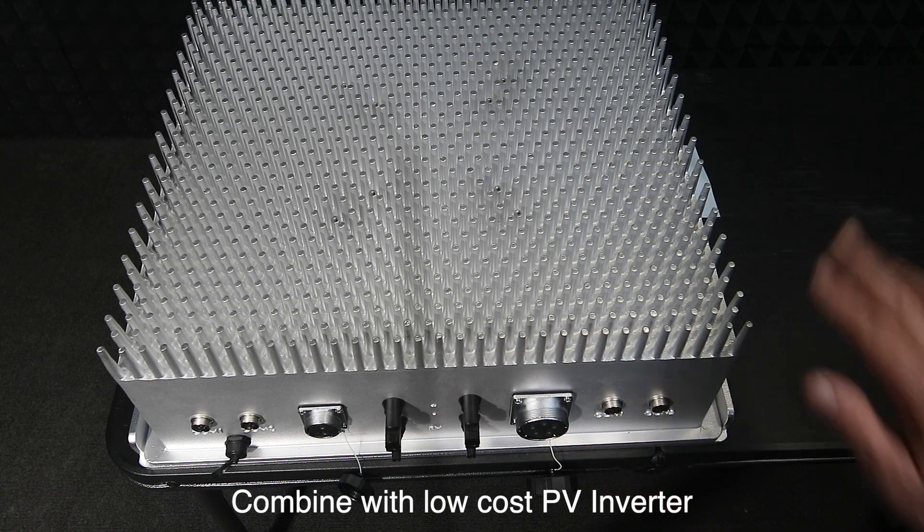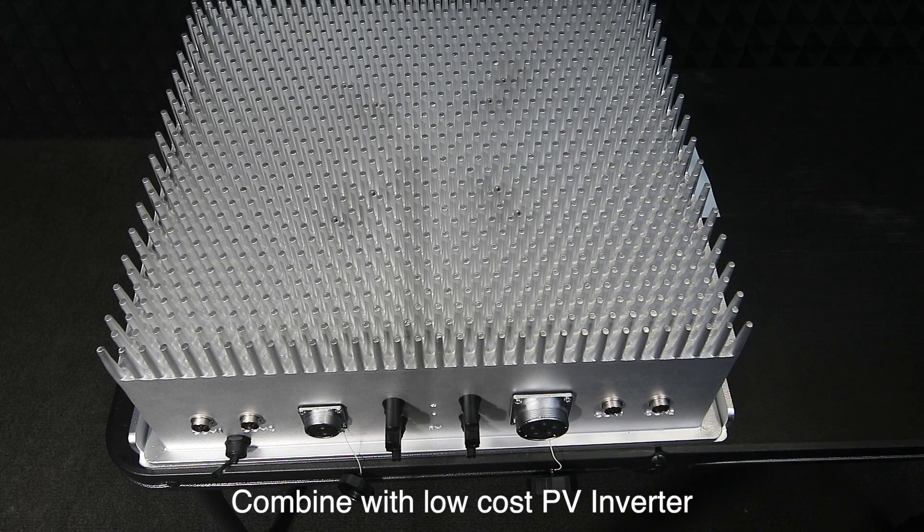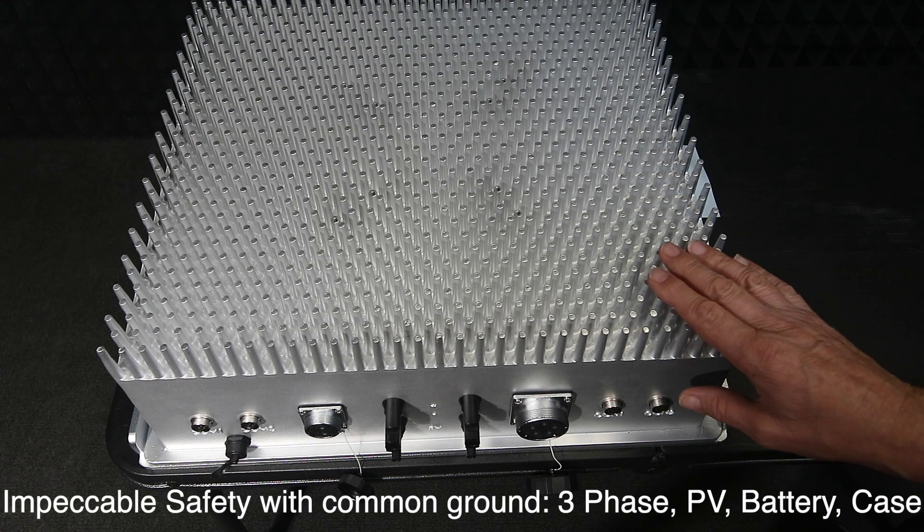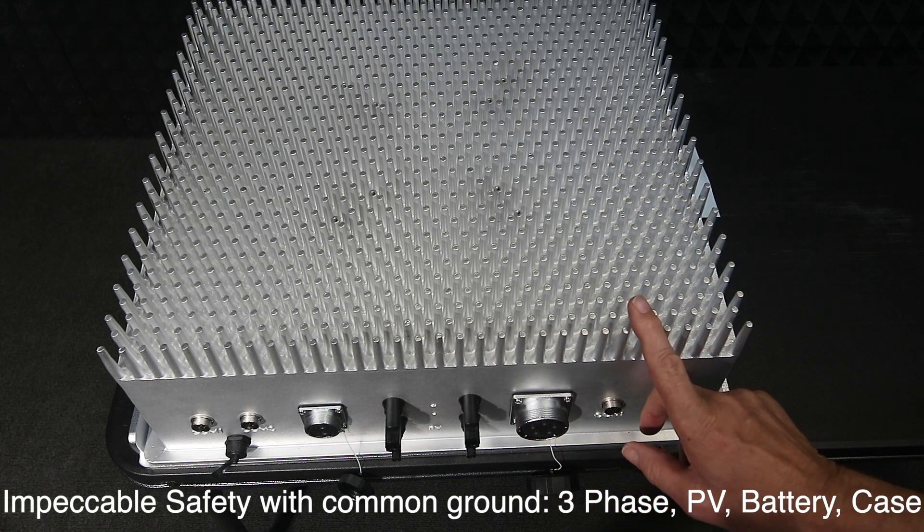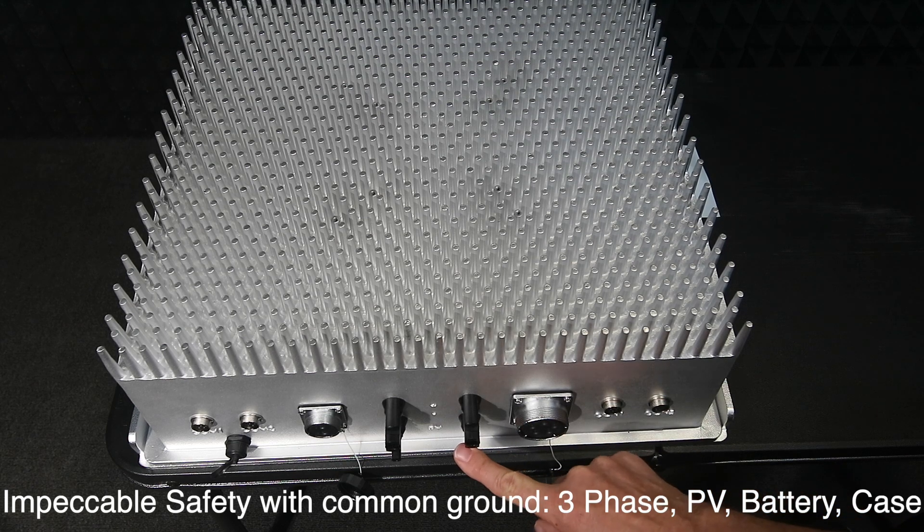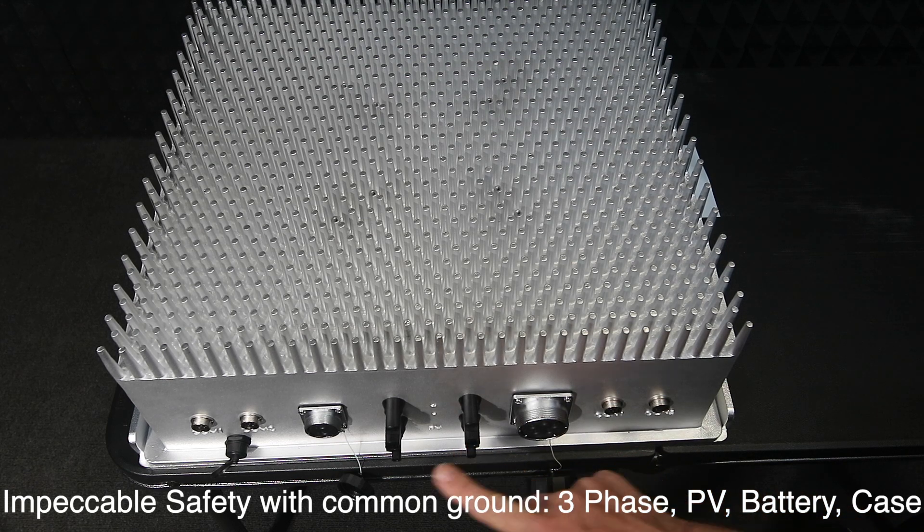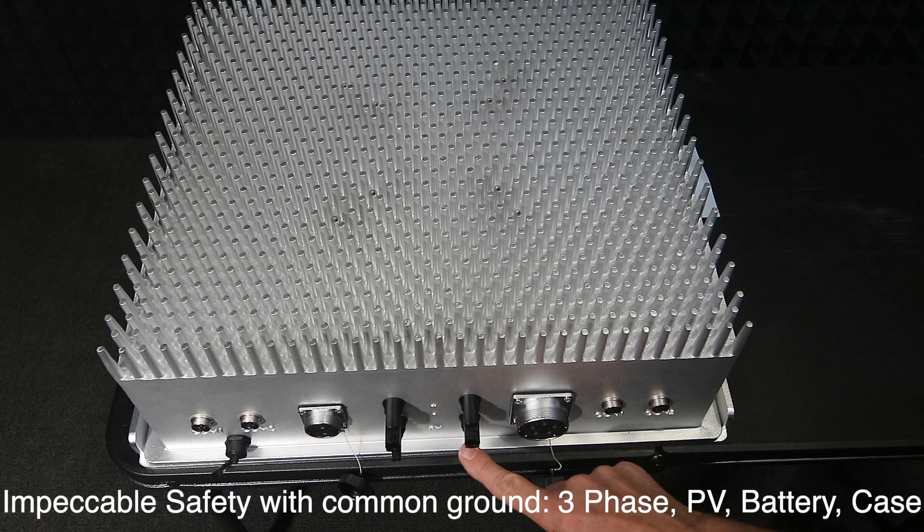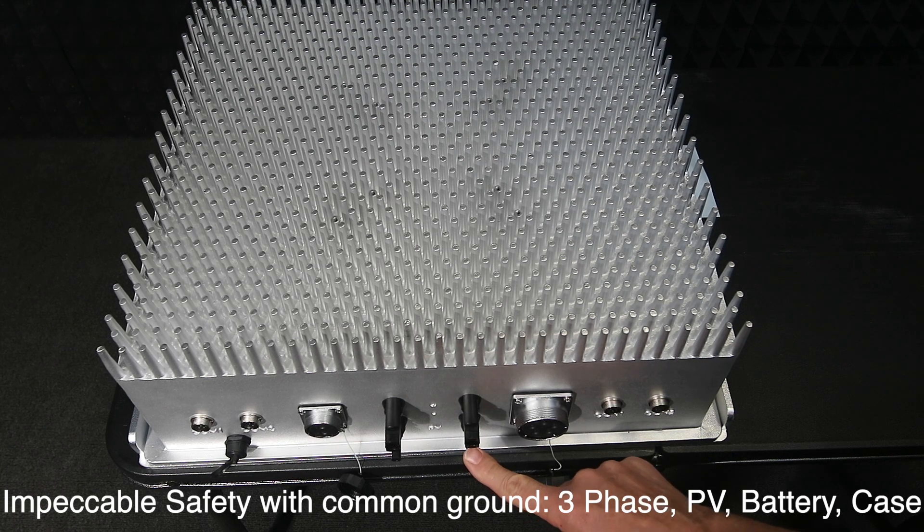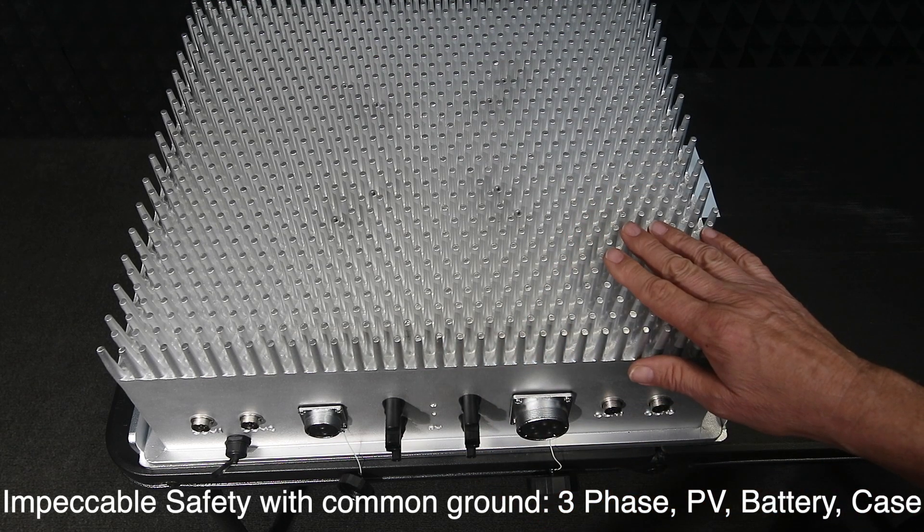An incredible safety feature here is that the neutral on the three-phase, the PV neutral or negative, the battery negative, and the case are all a common ground. So unlike a lot of inverters where the PV is not grounded, in this particular unit it's grounded.